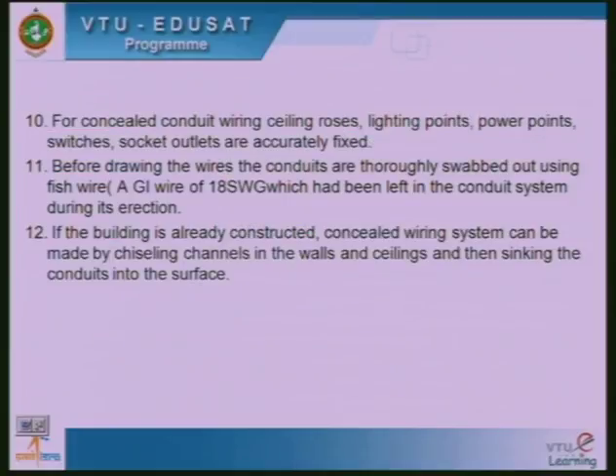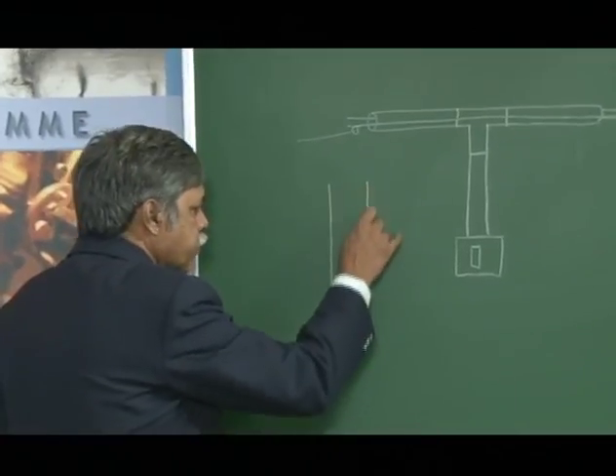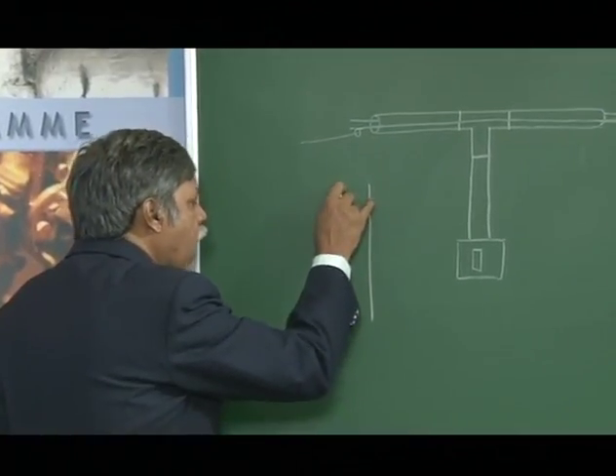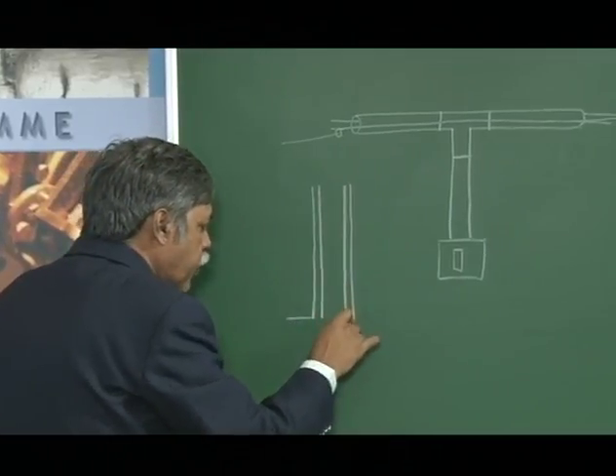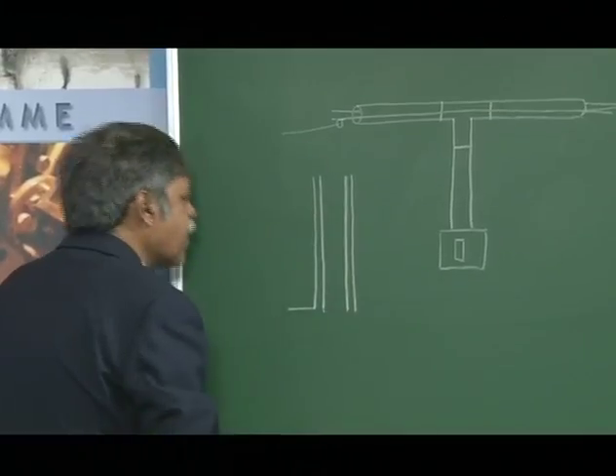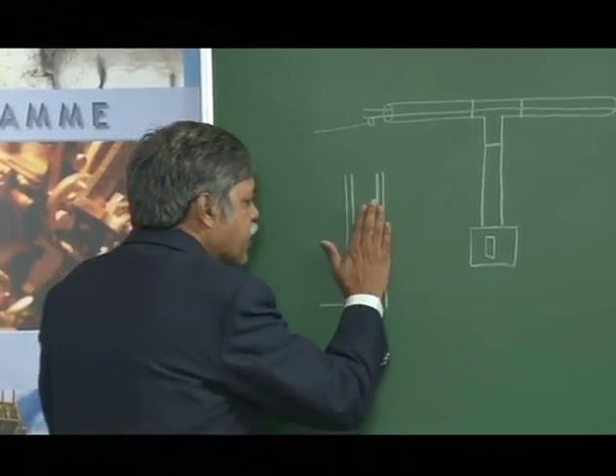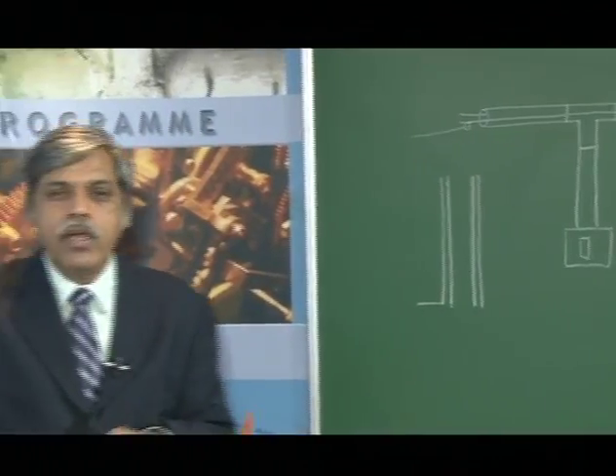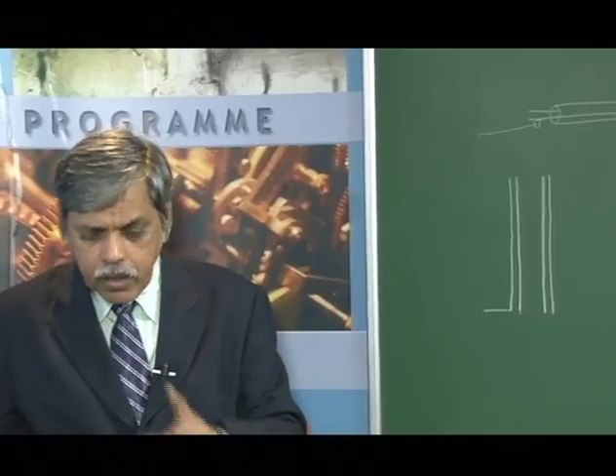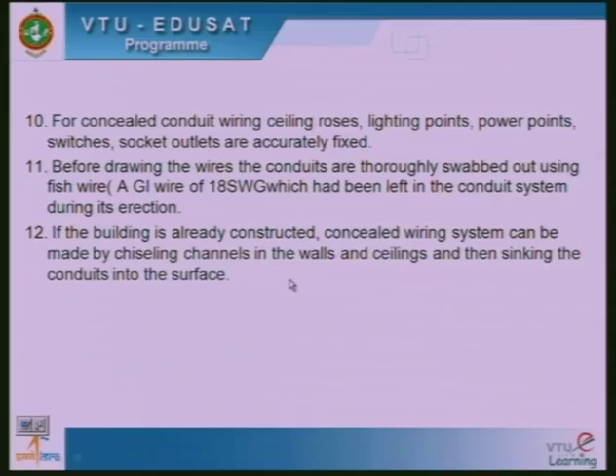Now these wires have to be brought to the switch boxes, which are normally fixed to the walls, okay. So at the point where the conduit is available at the ceiling, there should be one more conduit which runs to the switchboard. So they just chisel out the wall, okay. When I chisel out the wall, I will get a groove inside it. After getting the groove in the wall, I will put the conduit. After putting the conduit, I will plaster the wall. So after plastering, the conduit is not visible to you, okay, because it is concealed in the wall. So this is the 12th point I have said.